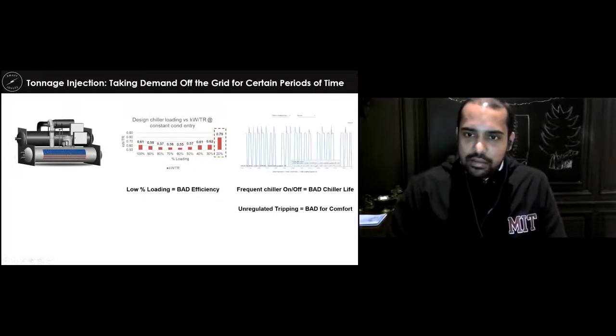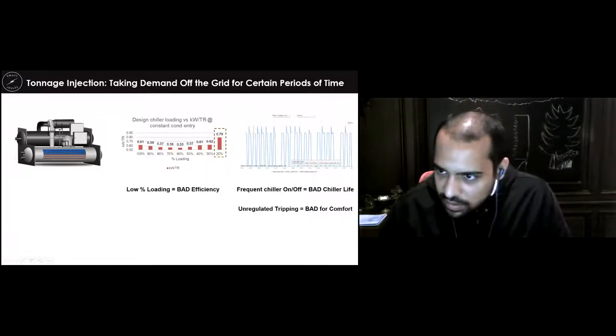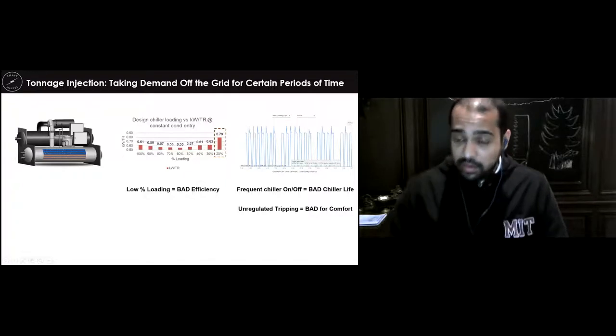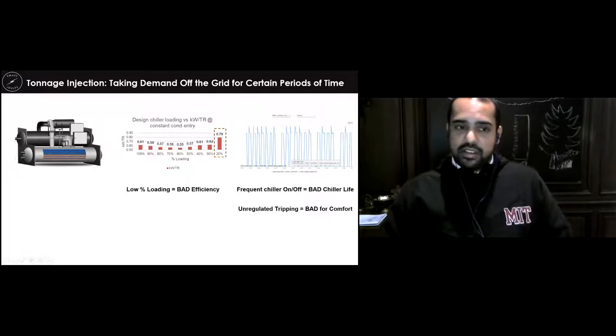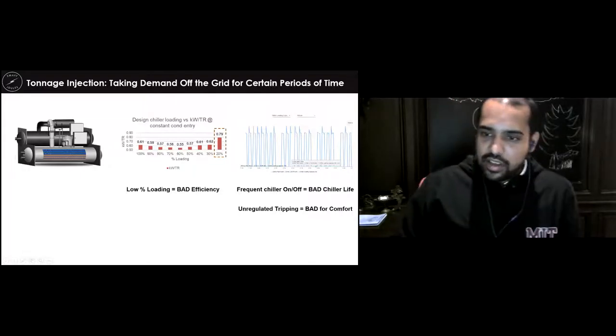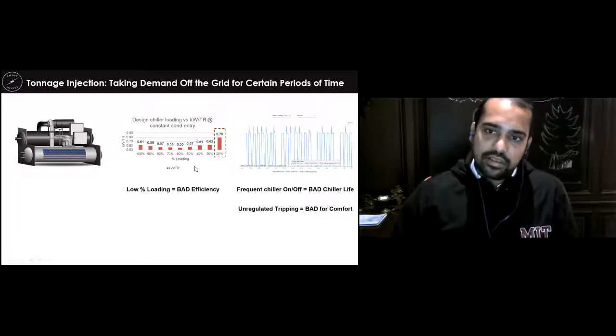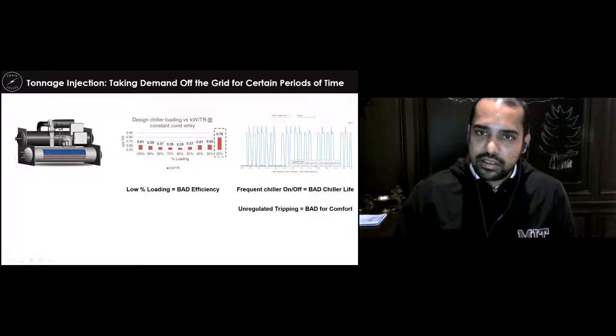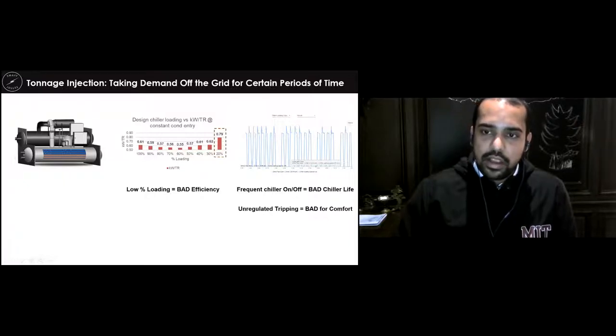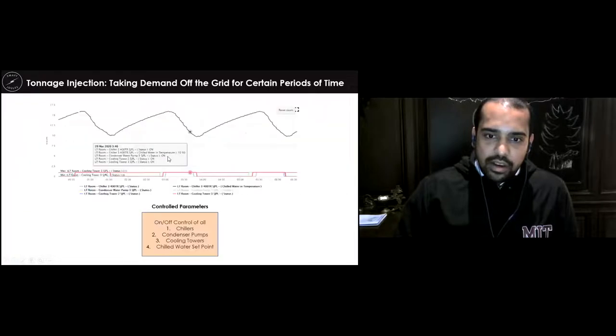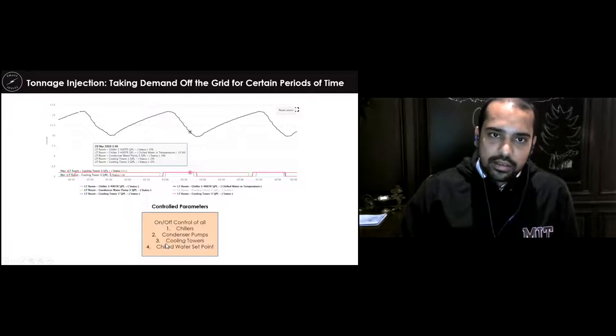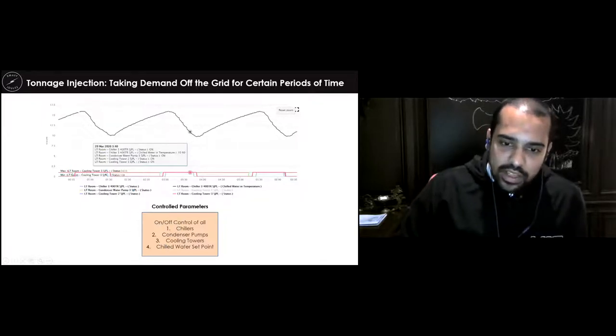The other thing you see is that when you have such low loading conditions, there is frequent on-off. Look at the number of times that the chiller is on and off, more than 20 times within a 2 hour window. That's not good for the compressor. It's bad for the chiller's life, and unregulated tripping is bad for comfort as well. You don't know how to manage this. It's a real nightmare for the people who are using it, especially when you have sensitivity to the temperature and humidity requirements. So we take some of these facts into account, and what we did is we came up with a method to control all chillers, all condenser pumps, all cooling towers and the chilled water set point. So this is a tonnage injection. So control all of these things.